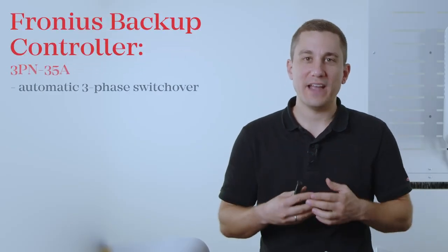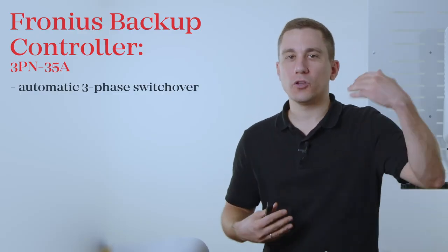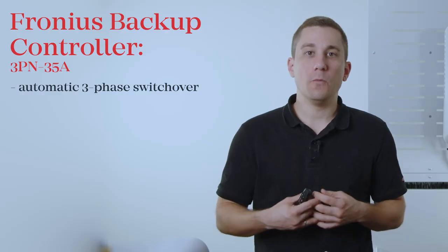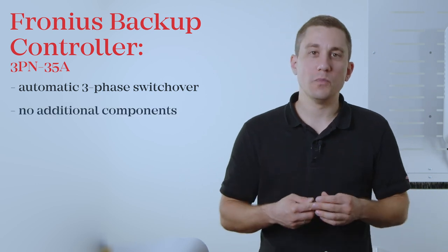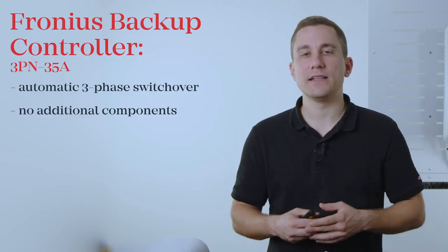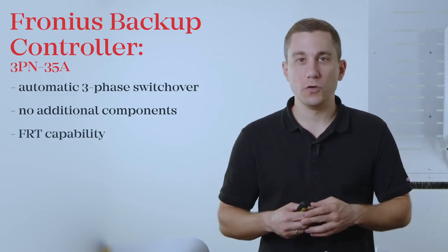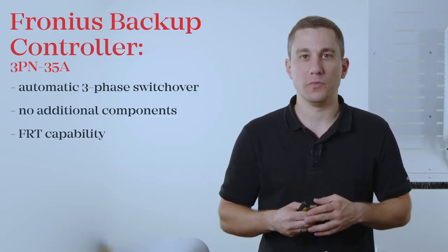In this video we are going to show you how to install and commission the Fronius Backup Controller. With the new Fronius Backup Controller you now have the possibility of a very simple and compact full three-phase switchover in your household. The Backup Controller will fully automatically switch over to Backup Power mode whenever the public grid fails. The controller already includes all the components you need for a full Backup Power solution, including FRT capability, without requiring any external switchover boxes or additional components.